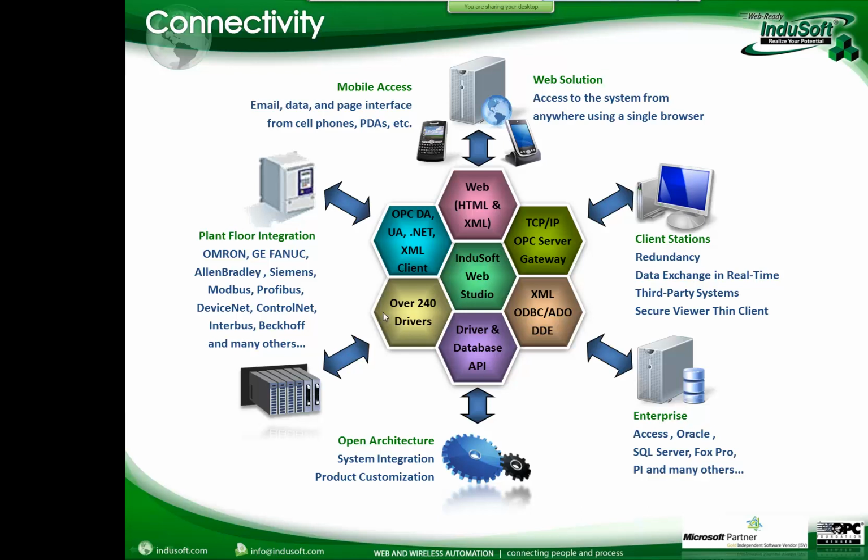So we provide with the product over 200 communication drivers to all sorts of PLCs that you have on the market. It goes from Allen Bradley, Siemens, Omron, GE, Fanuc, Beckhoff, CodeSys, some common protocols such as Modbus over Ethernet, BACnet. So all those different devices we do provide as part of the product communication drivers. But we also provide OPC interfaces in all possible OPC flavors, OPC-DA, OPC-UA, including on Windows CE, OPC.NET, and XML. We have clients, and we also have an OPC-DA server.